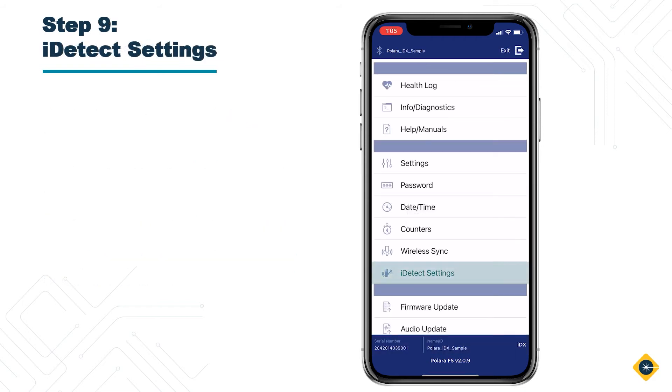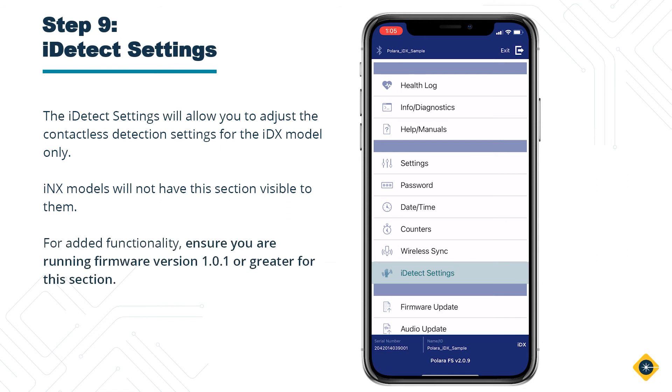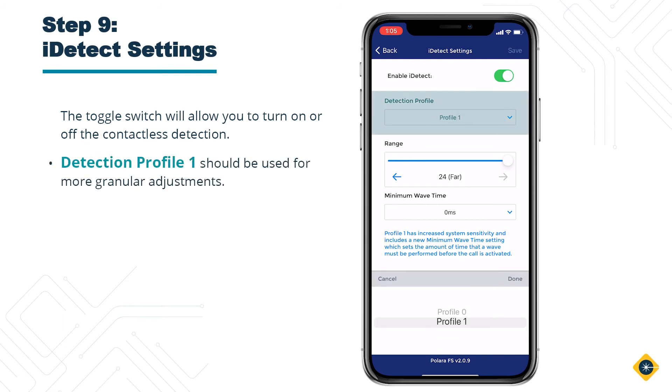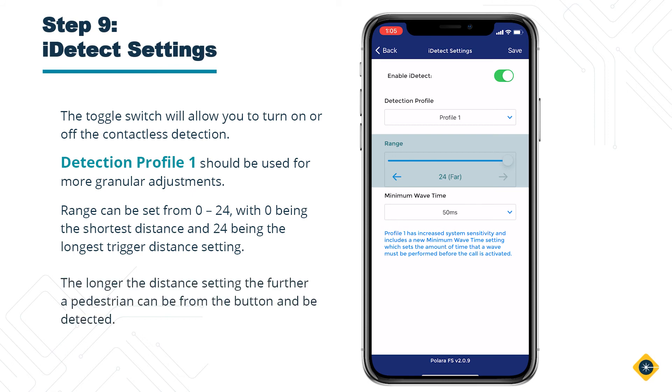Step 9: iDetect Settings. The iDetect Settings will allow you to adjust the contactless detection settings for the IDX model only. INX models will not have this section visible to them. For added functionality, ensure you are running firmware version 1.01 or greater for this section. The toggle switch will allow you to turn on or off the contactless detection. Detection Profile 1 should be used for more granular adjustments. Range can be set from 0 to 24, with 0 being the shortest distance and 24 being the longest trigger distance setting. The longer the distance setting, the further a pedestrian can be from the button and be detected.